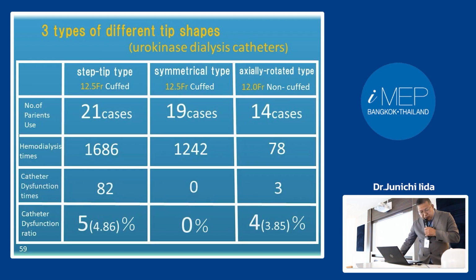We counted the need for reverse connection as catheter dysfunction. When reverse connection was performed due to poor blood removal under 80 milliliters per minute, reverse connection may sometimes occur two or three times continuously, but after those, the catheters were never completely unusable.